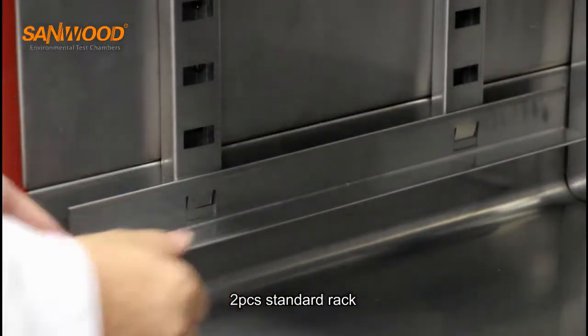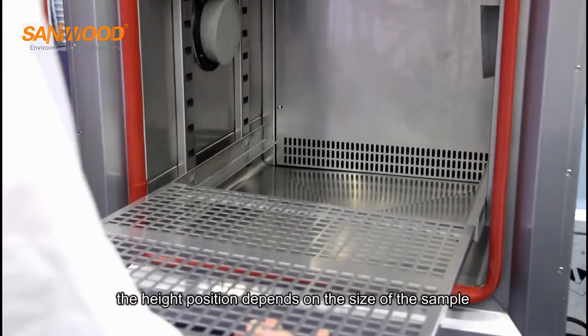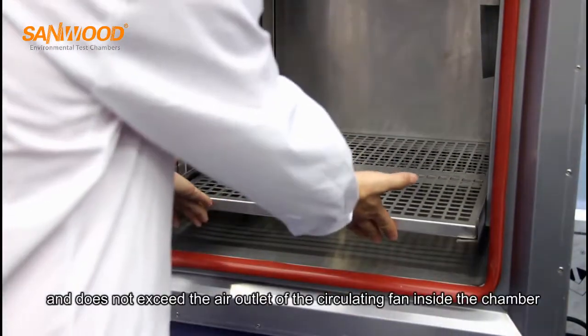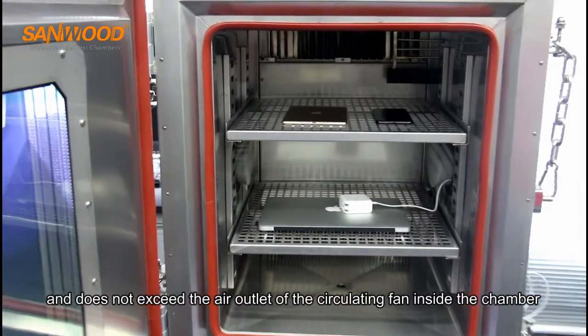Two pieces standard rack. The height position depends on the size of the sample, and does not exceed the air outlet of the circulating fan inside the chamber.